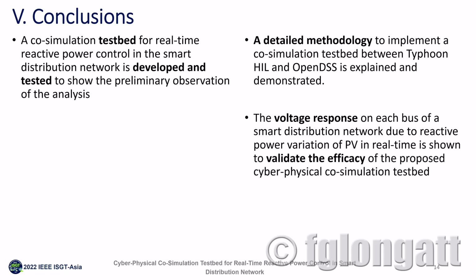As we showed during the demonstration using the CIGRE medium voltage distribution network, we demonstrate that when the voltages go beyond the regulation limits, the testbed can be activated to generate a signal to activate the real-time reactive power control.